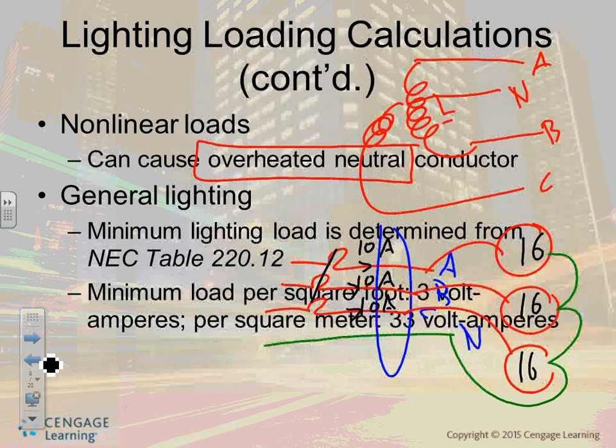Now, this is true if your equipment is not electronic equipment. This is true if these were motors, no electronics on them. It's true if it's heaters. The minute that you put electronic equipment in between, which in this case is the ballast, all these electronic printers and plotters, your laptop and mine, guess what the neutral does.